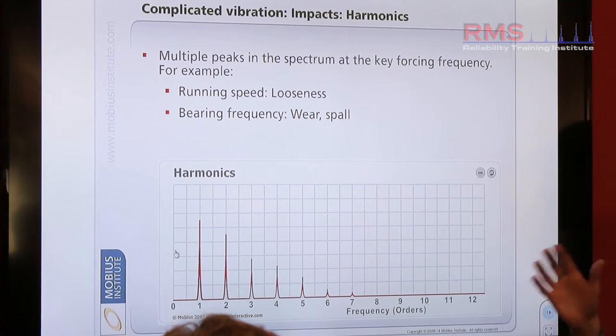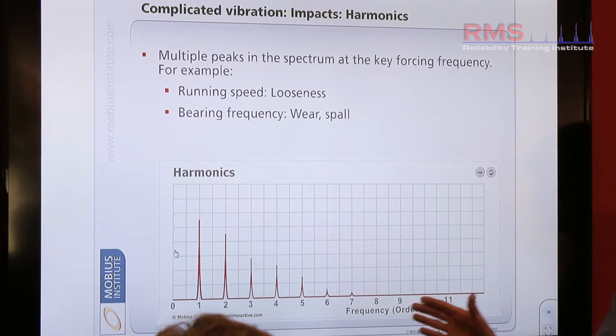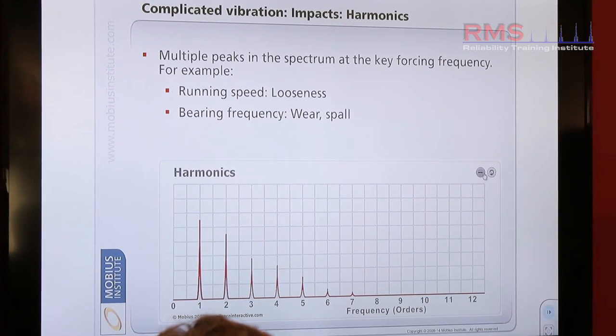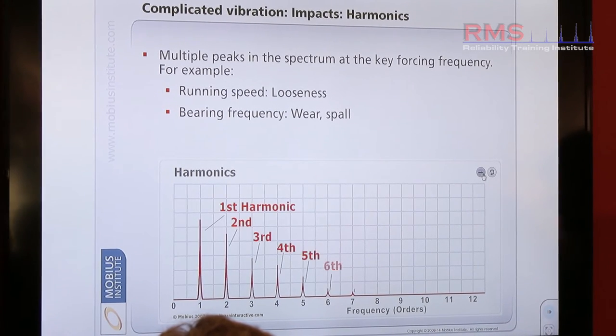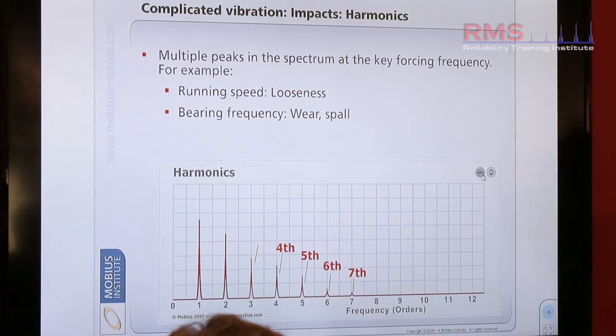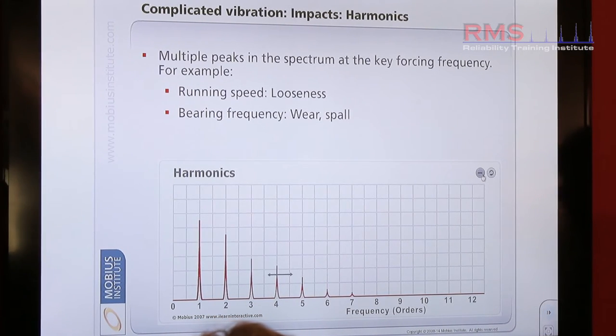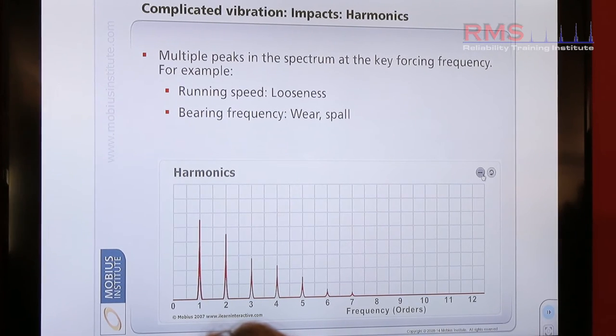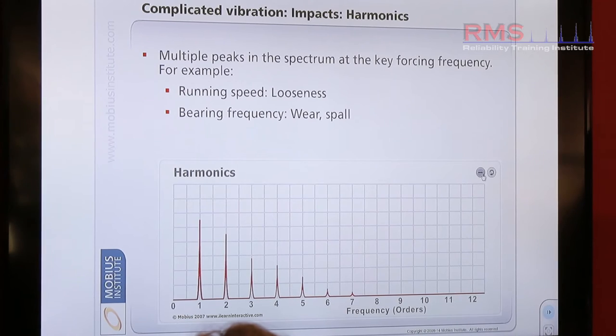That produces distinctly something uniquely different — characteristics that we call harmonics. Lots of them. Here we've got seven, and typically we see actually a lot more where something might be loose. Harmonics — like the echo kind of scenario — are equally spaced peaks that appear in the spectrum. Equally spaced peaks. So that's distinctly different to what you saw just now with a smooth vibration where there was only one single dominant peak.